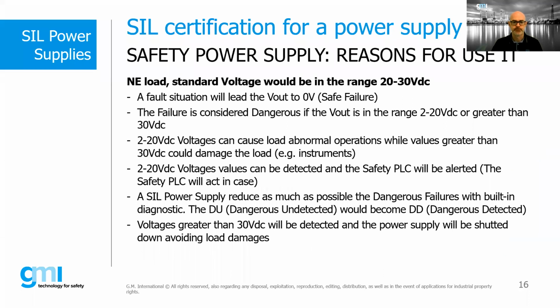Next slide, Andrea. At this point, why is it important to use a safety power supply system? First of all, we know that the standard voltage for a normally energized load is in the 20-30 volt DC range. As we have seen previously, conditions that lead to a power supply output voltage between 2 and 20 volts, or higher than 30 volts, are considered dangerous failures, which negatively affect the application. Well, a safety power supply significantly reduces undetected dangerous faults thanks to a built-in diagnostic system.